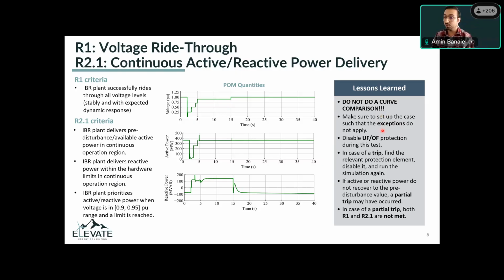Another thing is to make sure to set up the case such that the exceptions in requirement R1 do not apply. As JP mentioned, there are 4 exceptions for R1, including phase angle jump and V over F changes. So if you want to apply the LVRT curve, make sure that you just change the voltage magnitude, don't change the phase angle of the voltage, and keep the frequency fixed at 60 Hertz. That's going to make it easier, so that if you see the IBR plant tripping, then you know that it's not caused by those exceptions and it's caused by something that needs to be investigated.